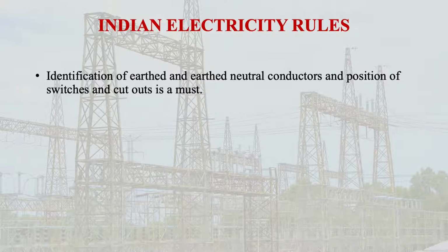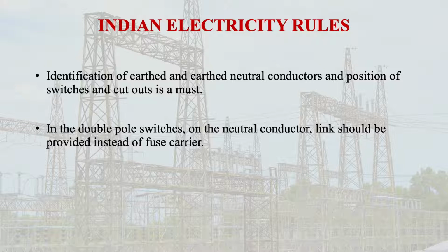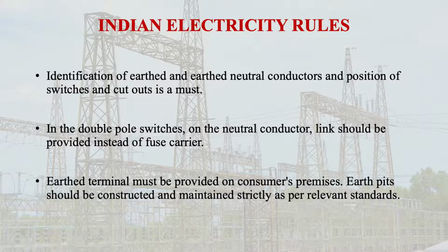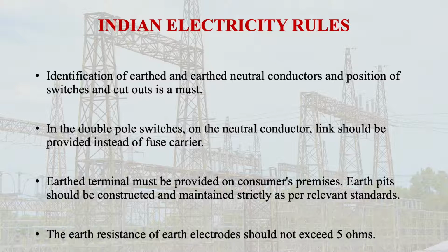Identification of earth and earth neutral conductors and position of switches and cutouts is a must. In the double pole switches on the neutral conductor, a link should be provided instead of a fuse carrier. An earth terminal must be provided on consumers' premises. Earth pits should be constructed and maintained strictly as per the relevant standards. The earth resistance of the earth electrodes should not exceed 5 ohms.